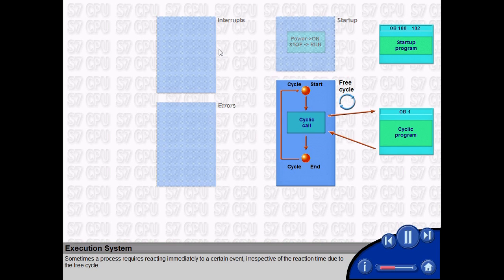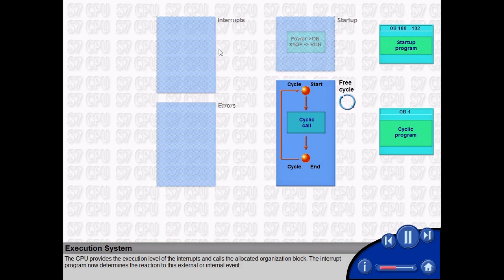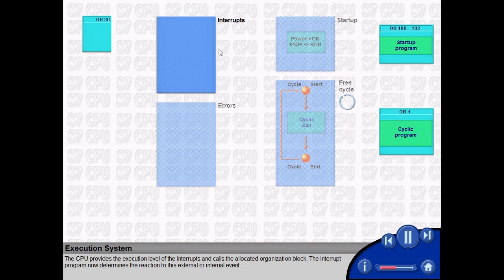Sometimes a process requires reacting immediately to a certain event, irrespective of the reaction time due to the free cycle. The CPU provides the execution level of the interrupts and calls the allocated organization block. The interrupt program now determines the reaction to this external or internal event.